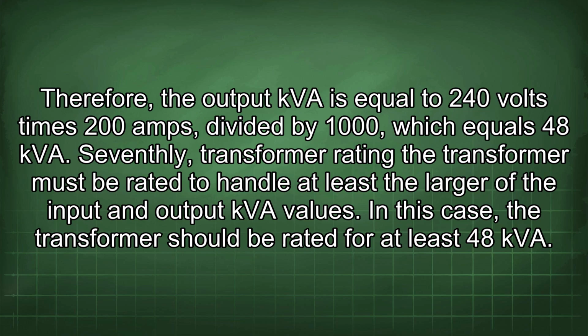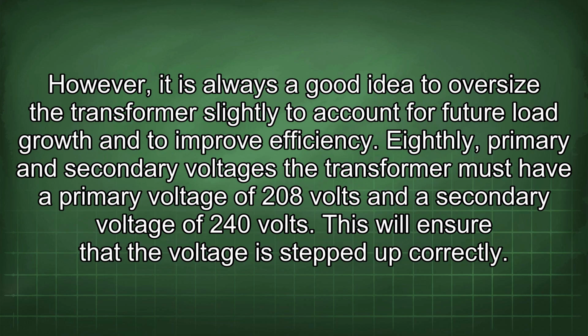Seventhly, transformer rating. The transformer must be rated to handle at least the larger of the input and output kVA values. In this case, the transformer should be rated for at least 48 kVA. However, it is always a good idea to oversize the transformer slightly to account for future load growth and to improve efficiency. Eighthly, primary and secondary voltages. The transformer must have a primary voltage of 208 volts and a secondary voltage of 240 volts. This will ensure that the voltage is stepped up correctly.